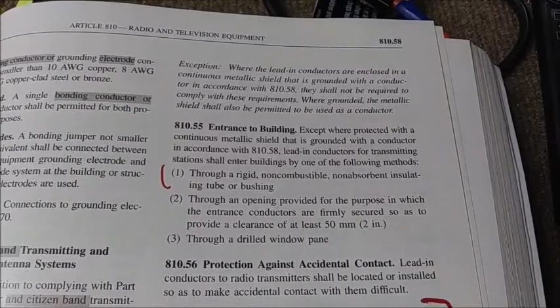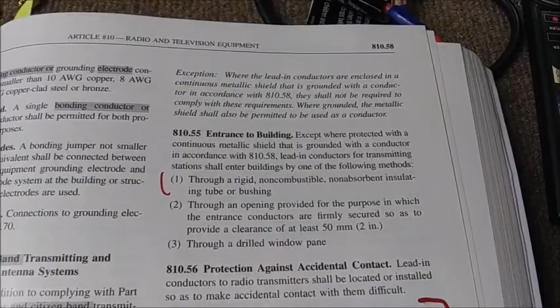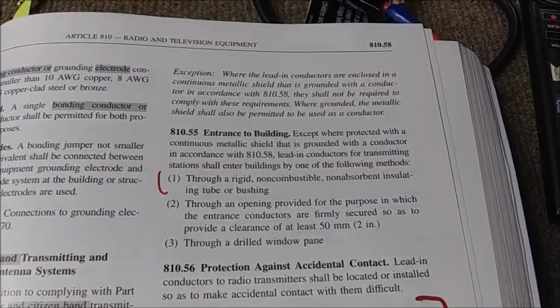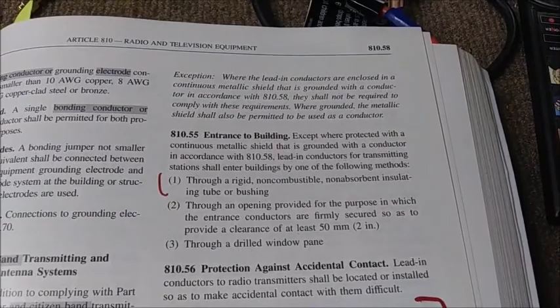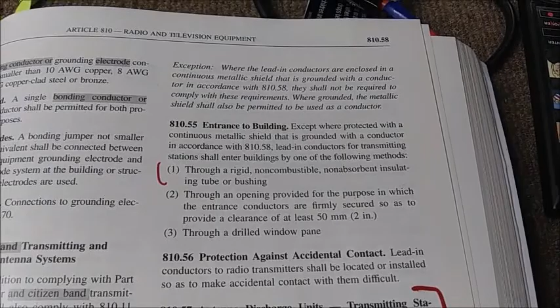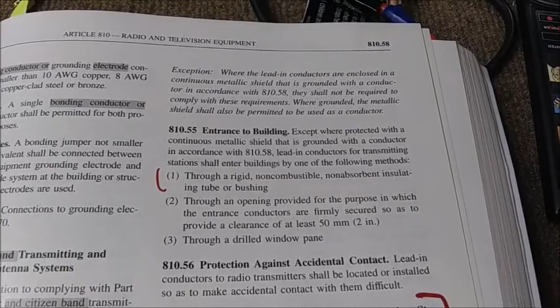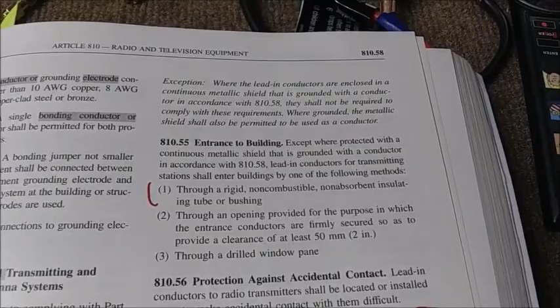Entrance to building. Except if protected by a continuous metallic shield, the braid on a transmission line is not a continuous metallic shield. Our feed lines at best are about 85% coverage. That is grounded with a conductor, yada yada yada. Lead-in conductors, plural, shall enter by one of the methods, etc., etc. This implies a pipe, not the coax shield.